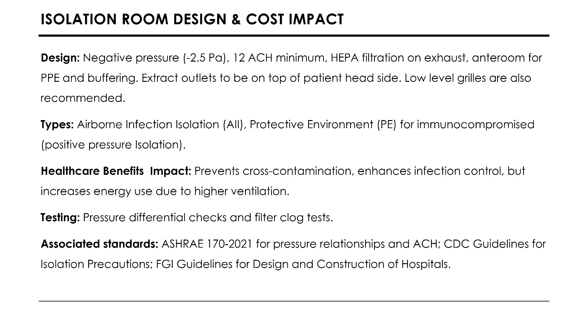No, that's wrong. A healthcare facility should not become a hazard for the staff working there. If a service engineer has to remove that HEPA filter, he gets contaminated because it's infected from patients. So the engineering also has to take care of staff requirements.